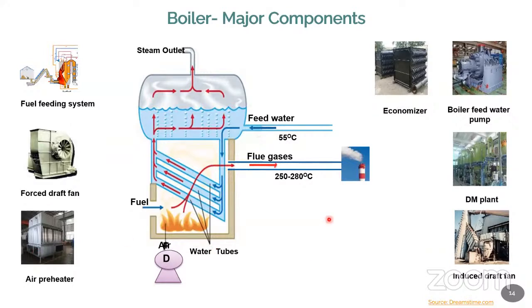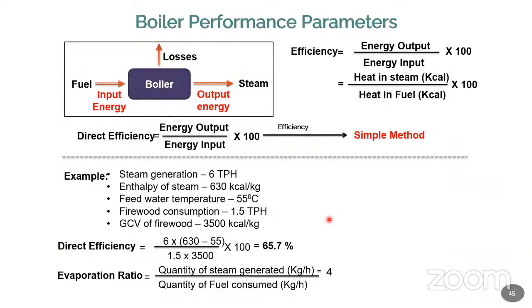Okay. Now we move on to the performance of the boiler. Normally, performance of the boiler can be evaluated by two important parameters. One is efficiency, another one is evaporation ratio. Efficiency calculation has two different cases. One is the direct efficiency method, another one is the indirect efficiency method. Of course, the indirect efficiency method is somewhat complicated, but it is accurate. Whereas the direct efficiency method is simple, but it is not accurate. It will give only an approximate value.